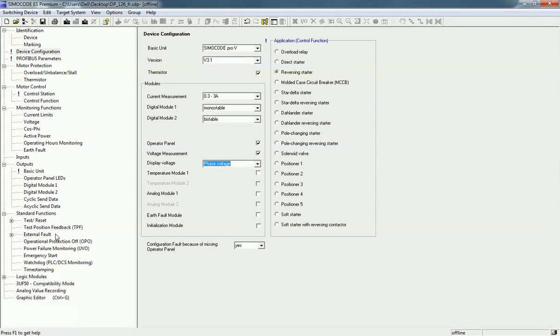If you are using extra temperature, analog, or earth fault modules, you can enable those options. On the right side there are different application or control functions available for the SIMOCODE kit. In our kit we have two contactors, so applications like reversing starter and direct starter can be configured. If you have three contactors and the required hardware, you can go for star-delta and other applications. For now, I will select the reversing starter option and we will see the reversing starter demonstration.